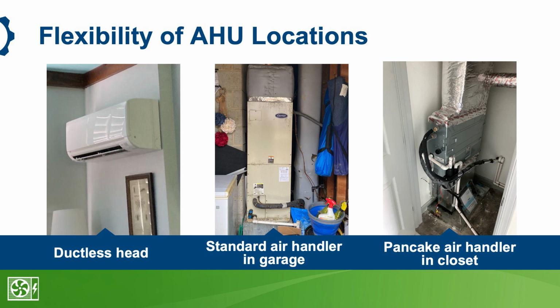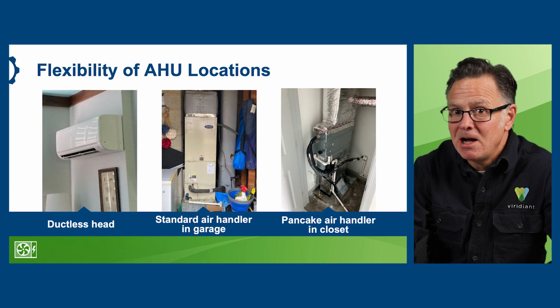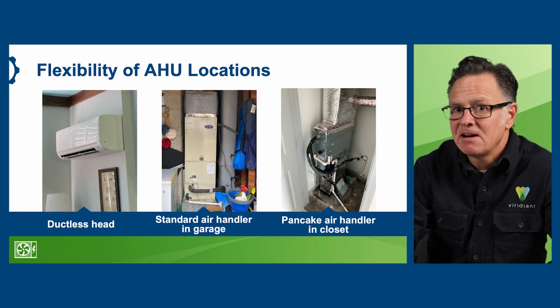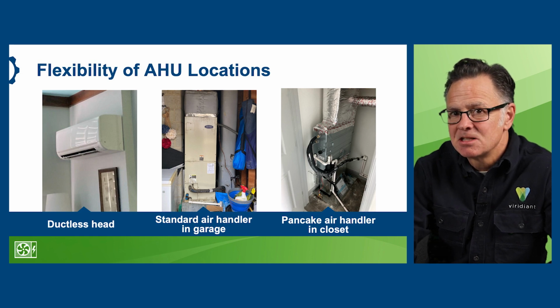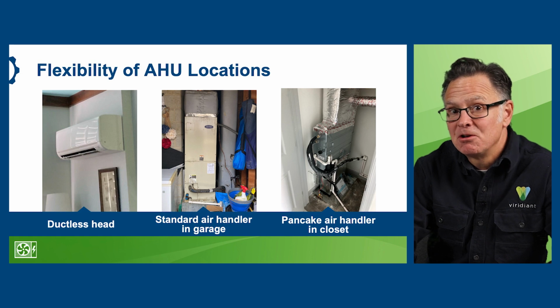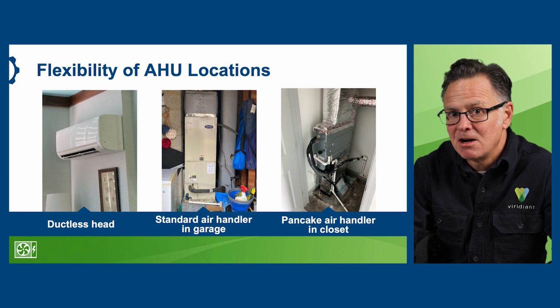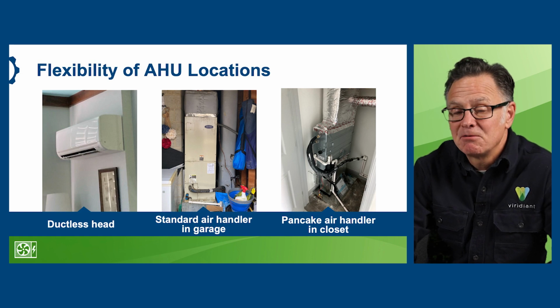They come in different sizes and styles, as we've discussed, and they don't require the venting of fumes. I will say that whenever at all possible, we do want to install the air handler and ductwork in conditioned space, not like that one shown in the middle, which is in an attached garage. And that principle would apply for fossil fuel equipment as well.